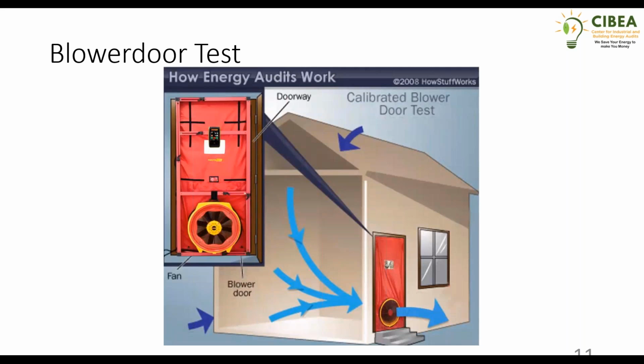If it is not a centrally air conditioned building, then the same test applies to each and every room where we have split air conditioning systems, either for heating or cooling. For every individual room, we measure the leakage rather than for the whole building at once. The test can also be performed by pressurizing, by pushing air in, and by ASTM and international standards, it is advised to perform the test twice, in both pressurized and depressurized form. But at the end, what we get is the level of leakages in the building.